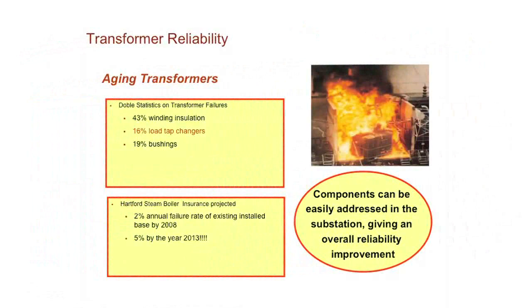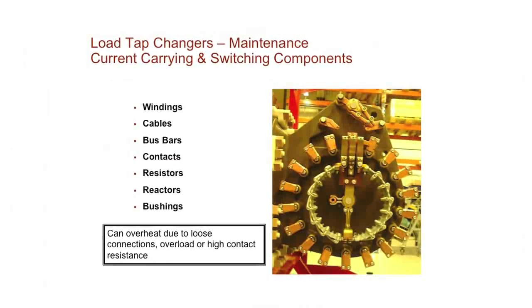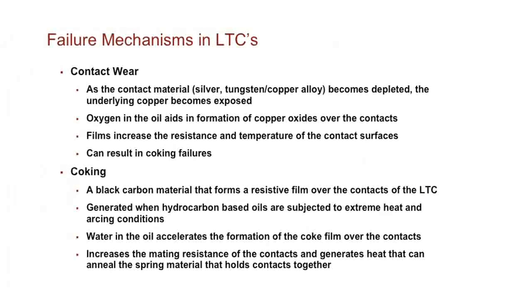Part of the transformer base, talking about load tap changers, they have statistics that 16% of transformer failures in today's marketplace are basically load tap changers. Part of that, LTCs, is the maintenance cycle of it. A lot of LTCs today, whether they're new or old, all of them require maintenance at some stage along the way, basically because you have windings, cables, bus bars, contacts, resistors, reactors, bushings, all of them have some capability connection to the LTC itself. Talk about contact wear.